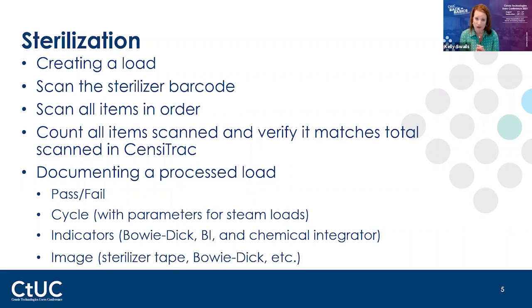Also, you want to make sure that full image is on there. As you close a lid on a document scanner, as that air escapes, many times it will move that tape, that Bowie-Dick test, or if you're scanning your chemical integrator into there, or even a wash test, it'll move, and now you've lost part of that image, or you've lost part of the information on the tape. So here's where you want to make sure that you're viewing that, especially your text, because it saves them a conversation with leadership if something's wrong. So make sure everything's in there, everything's beautiful, and they can read everything.